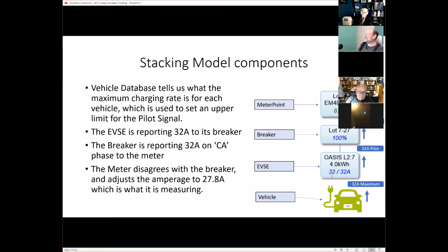Currently, this picture shows that we are offering the car 32 amps out of the 32 amps that are possible to send to this car. This EVSE reports up to the virtual breaker, saying that we're using 32 amps of a pilot signal from the EVSE to the car. The breaker now knows 32 amps are being used, and this breaker is a 40 amp breaker, so it's allowed to use 32 amps. So we are 100% full of what has been allocated. The breaker then reports up to the meter point that we're using 32 amps, and because the breaker is on phases CA, it reports that up to this meter point.